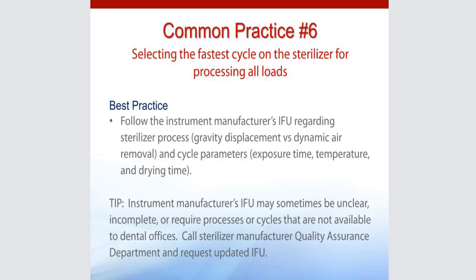pouch. So you want to make sure that you are following your instrument manufacturer, your sterilizer manufacturer's instructions for use for the appropriate cycle parameters, meaning time, temperature, pressure, as well as dry time. If you have an older, like I said, a workhorse unit, and some of those IFUs aren't as detailed, I would encourage you to contact the manufacturer and ask them for updated IFUs. You can usually call the quality assurance department. Sometimes even customer service can help you with that.